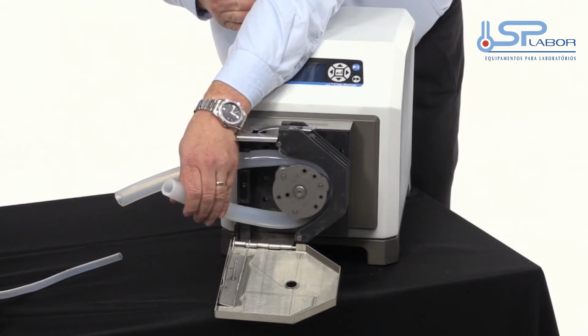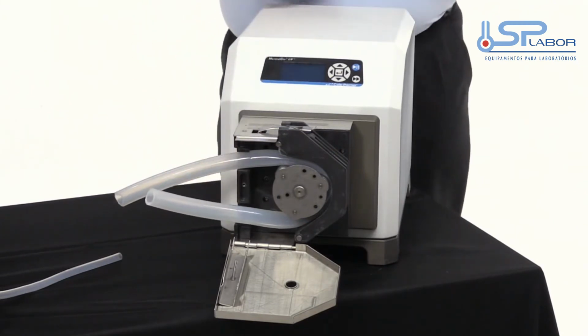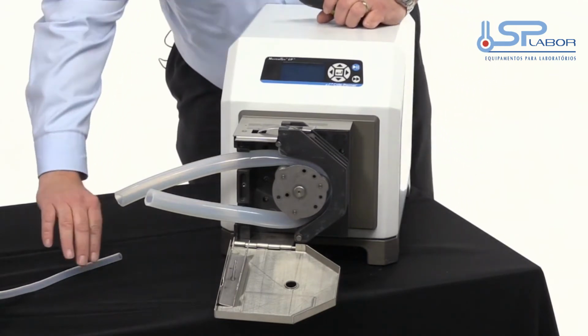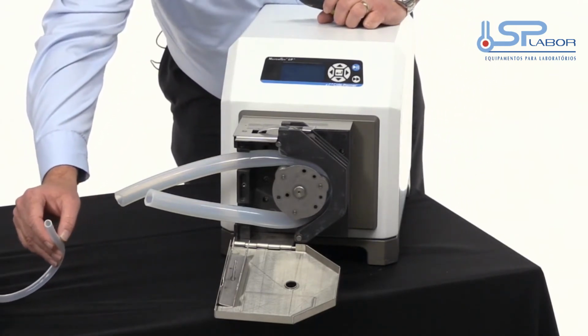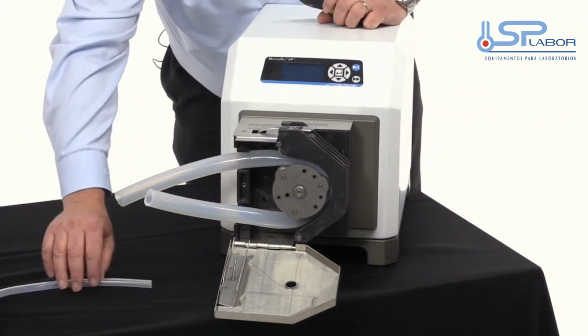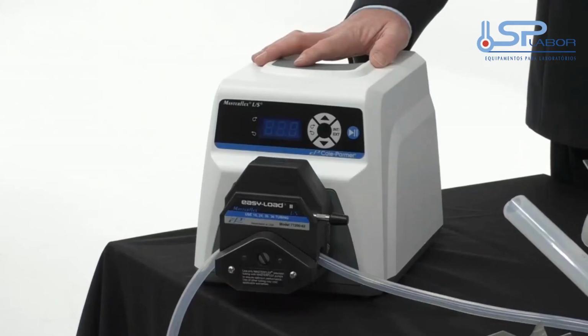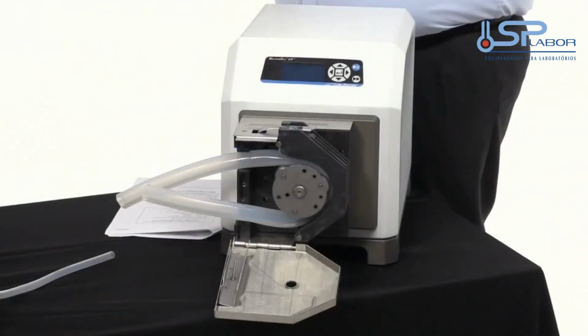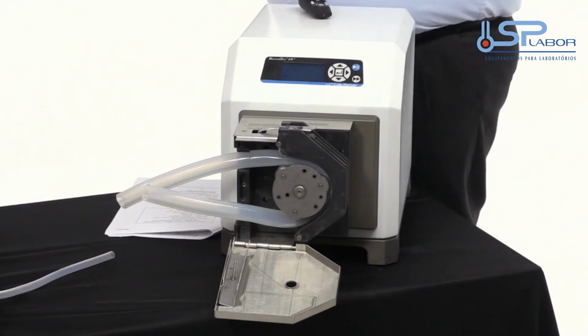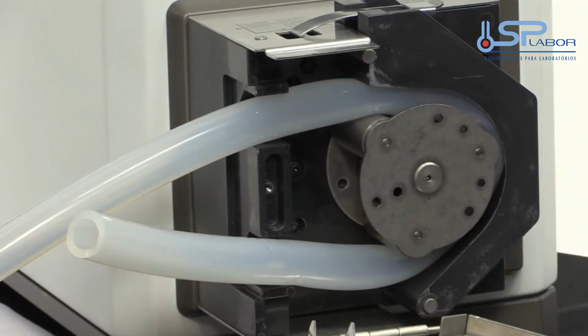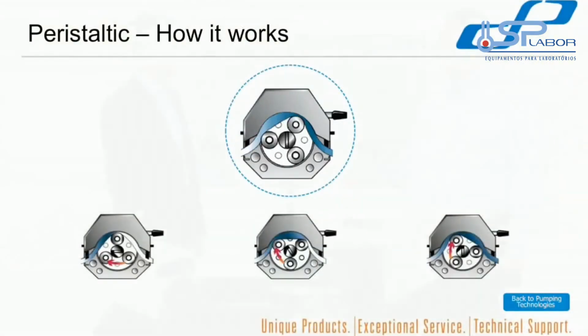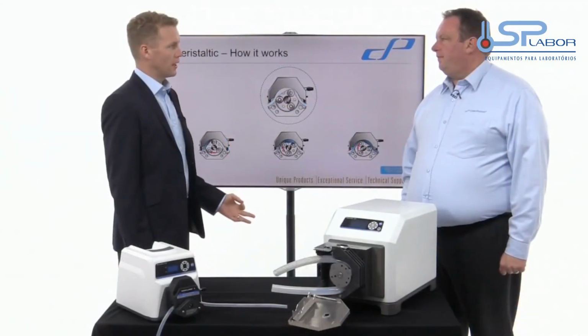The pumps go in speeds from 0.1 RPM up to 600 RPM on the smaller ones. The larger ones have a lower top speed, because it's about squeezing the tube and then allowing the tube to actually reopen and reform. If you do it too fast, you wouldn't allow the tube to reopen. So Colin, is this an evolving pump technology?